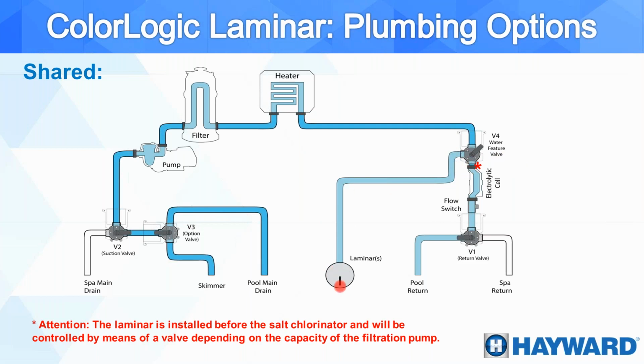If it is only one or two laminars, we might be able to power them with the standard filtration pump that we already have. Remember that we will need a cartridge filter in that case, no sand, because sand doesn't give us the fine filtration that we require for the laminar.